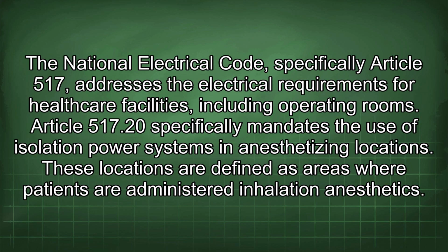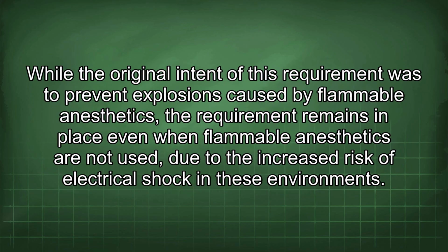The National Electrical Code, specifically Article 517, addresses the electrical requirements for healthcare facilities, including operating rooms. Article 517.20 specifically mandates the use of isolation power systems in anesthetizing locations. These locations are defined as areas where patients are administered inhalation anesthetics. While the original intent of this requirement was to prevent explosions caused by flammable anesthetics, the requirement remains in place even when flammable anesthetics are not used due to the increased risk of electrical shock in these environments.